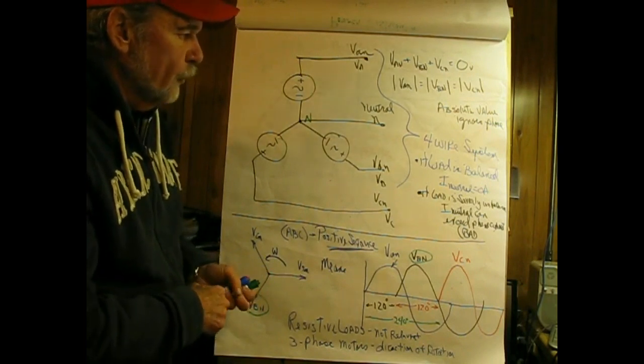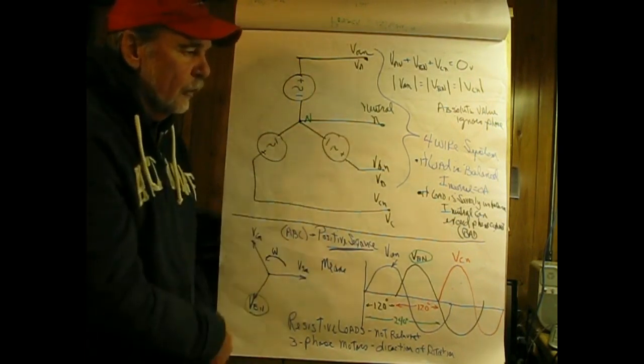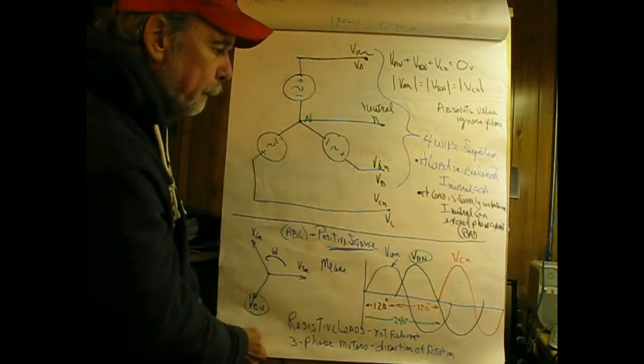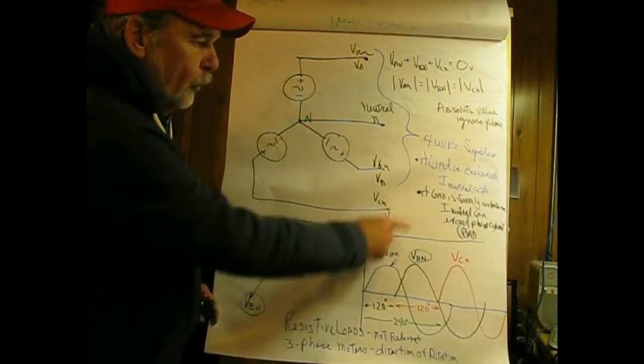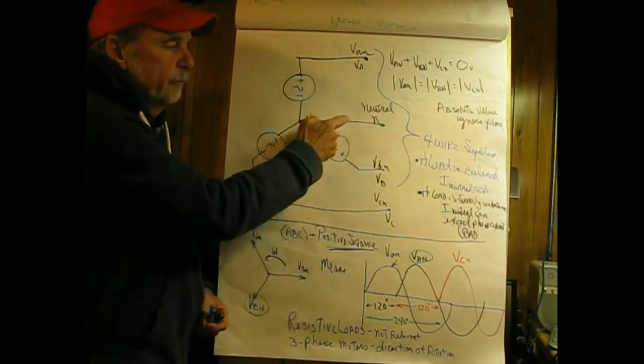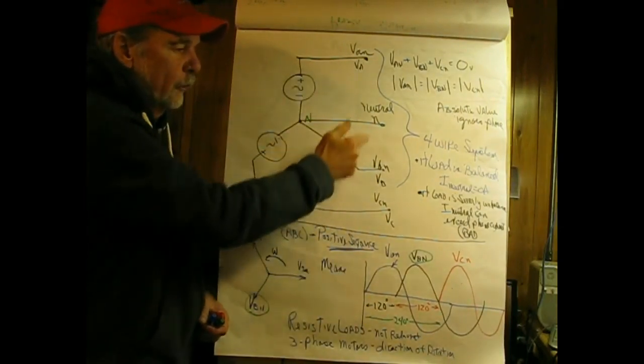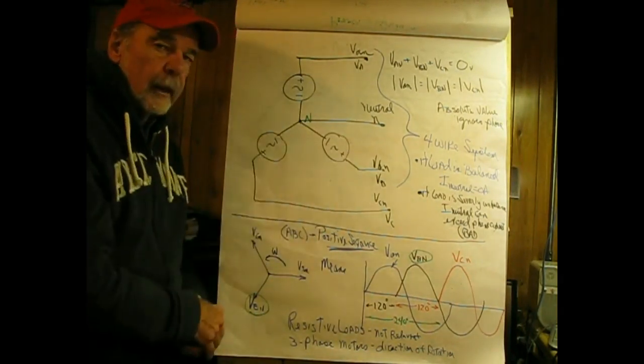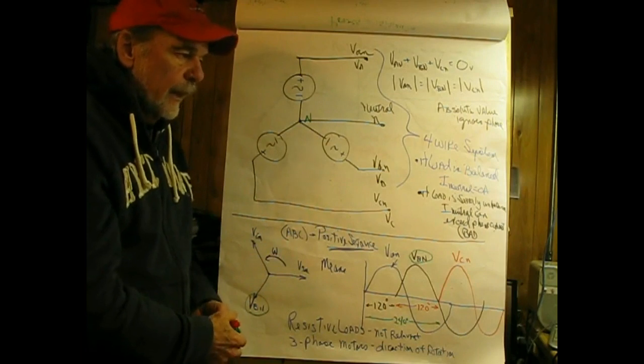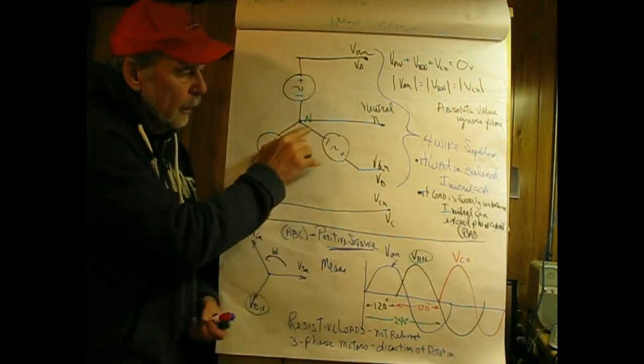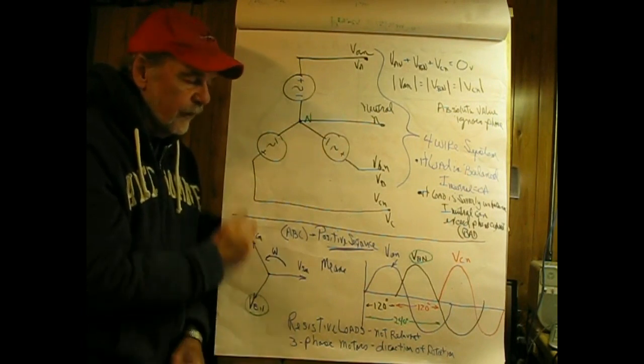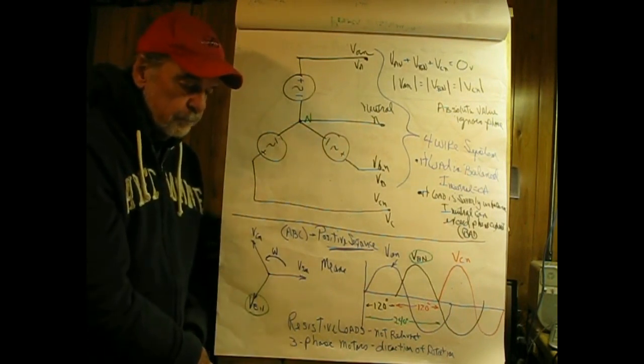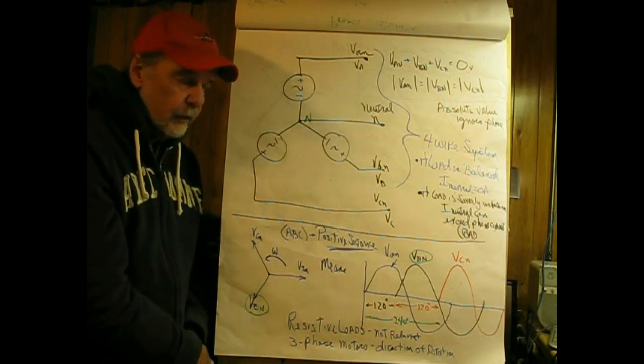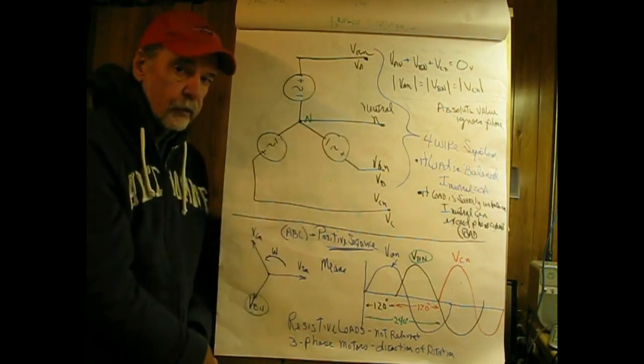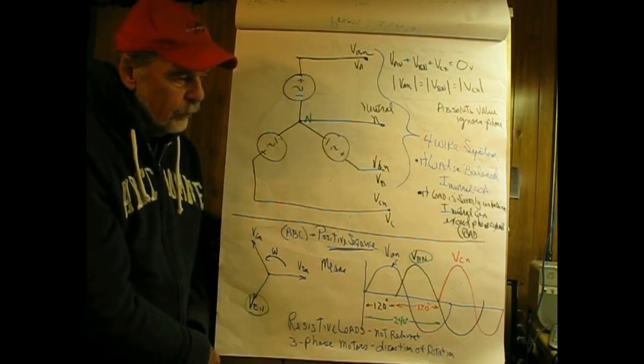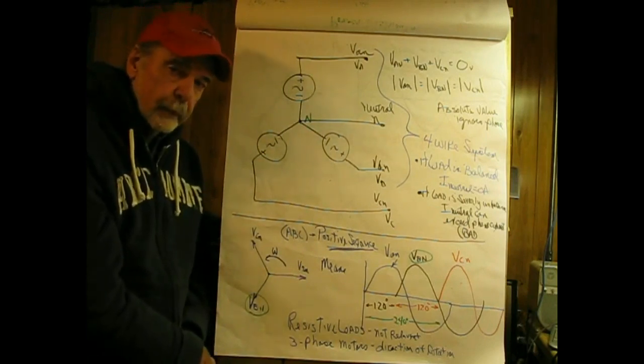So, in a 4-wire system, what we would have would be the 3 phases and the neutral. If also the load is severely imbalanced, that means that the load between VA and neutral, and VB and neutral, and VC and neutral is very, very much different. That's not a good thing, because the neutral current can actually exceed the phase current. And in recent publications by the NEC, they're suggesting to oversize the neutral wire. And there's another issue in there that's referred to as triplens.